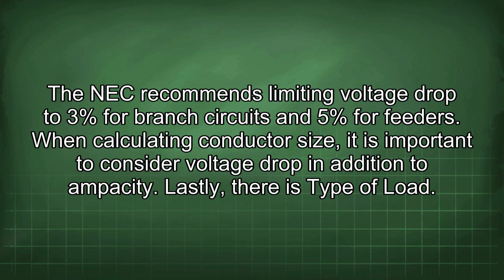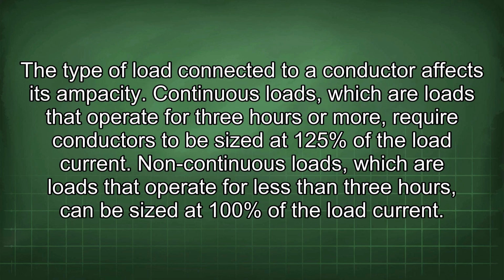The NEC recommends limiting voltage drop to 3% for branch circuits and 5% for feeders. When calculating conductor size, it is important to consider voltage drop in addition to ampacity. Lastly, there is type of load. The type of load connected to a conductor affects its ampacity.